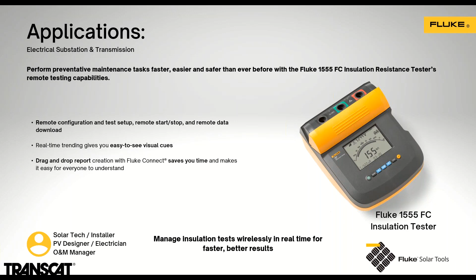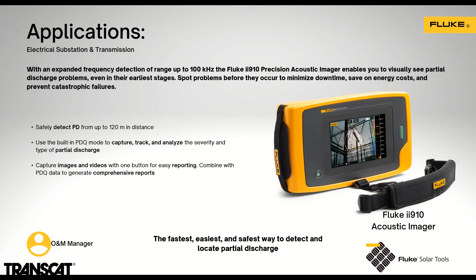And then finally on our applications, an II-900 or a 910 is going to allow them to analyze if they have any substation or transmission issues. We've really walked through the whole process of the solar installation, from the panels themselves and what they need with the irradiance meter, all the hard connections, having the MC4, moving through the combiner boxes, the voltage, the current, any of the insulation that they need to make those hard connections in the ground, analyzing the inverter, any output with the power on the power quality side, our battery analyzing, and finally that next step, getting into the transmission aspect of it, and if they're having any problems with that, which could cause backfeeding into the whole entire system. So Fluke has really offered a total package of solar solutions out there in the field from a multitude of whatever level of technician you are, that solar installer, all the way to the operations and maintenance manager.